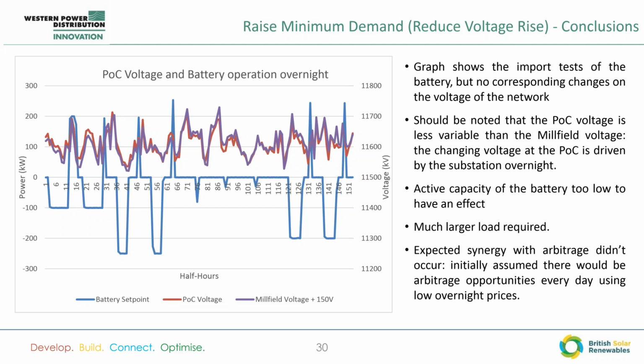Admittedly, the visibility of this use case is not helped by the fact we are on a live network, which in some ways is the point, but there's a tap changer that is independently deciding when to change over at the substation. We don't have visibility of that. There's a constantly changing amount of loads, and we don't have second-by-second monitoring at Millfield. Every half hour was the closest we could get.